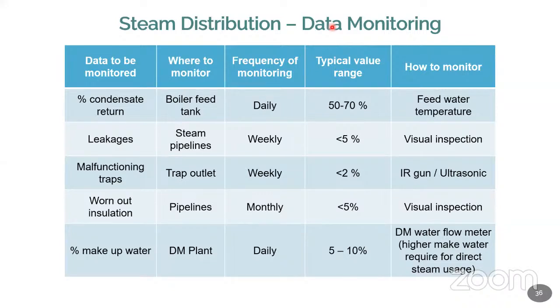In the steam distribution system, these are all the points to be always monitored. What is the condensate return? I need to monitor the feed water tank. How much condensate is going to be returned? Normally 70% of the water will be returned. 70% of the steam will be returned normally. So 30% is the makeup water. It depends on the process.